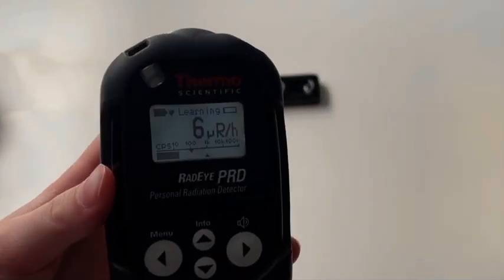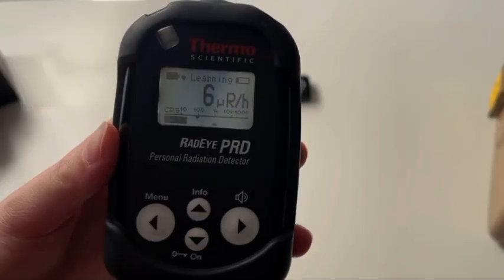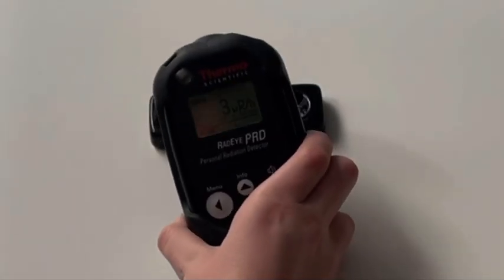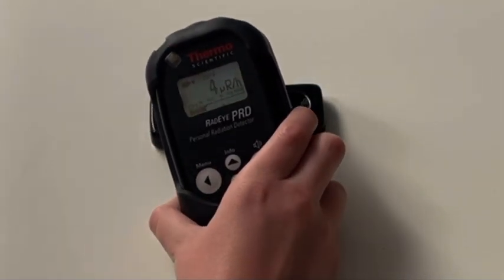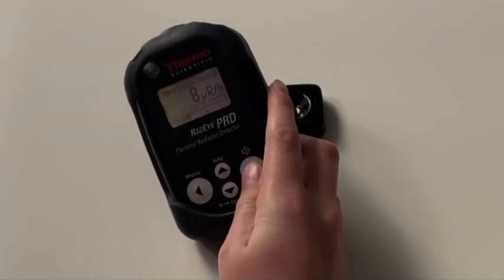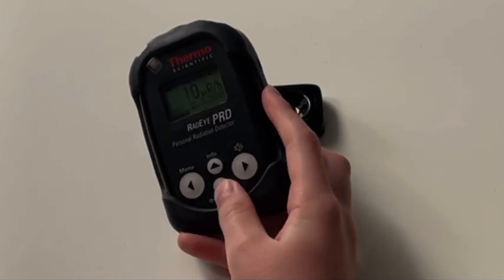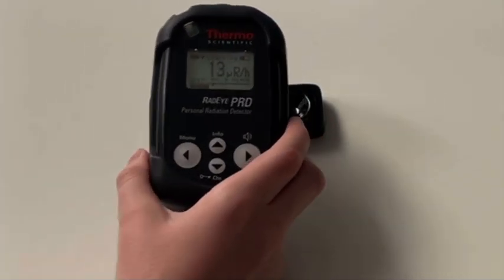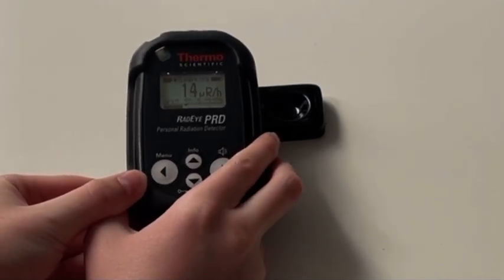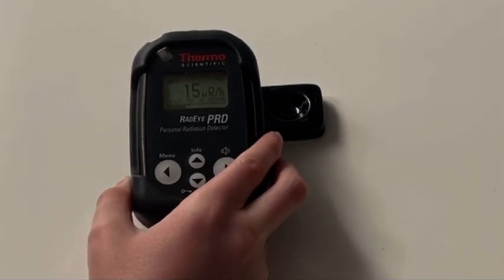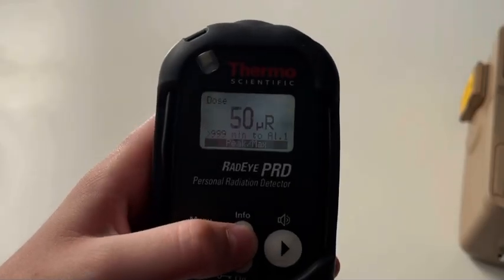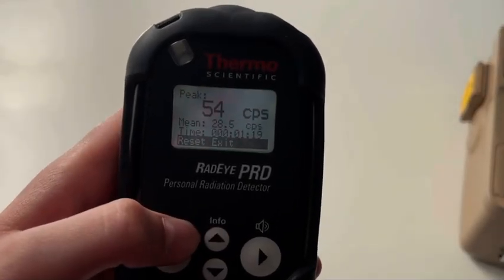Our next meter for measuring this radiation is the Radeye PRD, which is a gamma scintillation detector using a NaI(Tl) crystal. 15 microroentgen per hour. Peak count rate was 54 counts per second.